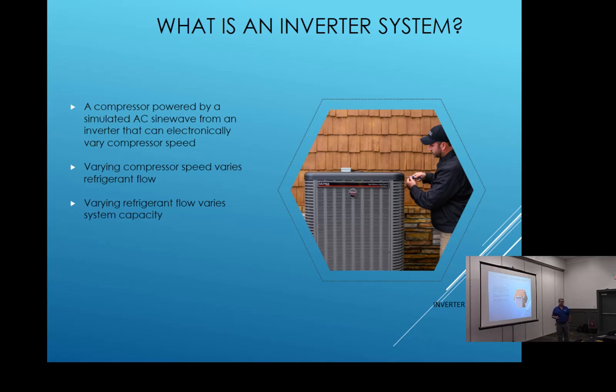Okay. Really, what we're doing is we're varying the hertz to that compressor. Just like a VFD drive, 60 hertz on the VFD drive is 100%, right? And if we go and turn the hertz down on that VFD drive to 55%, that blower, we slow it down to 50, it goes slower. Same thing. It's just varying it the whole time, okay, is what that basically is, in plain language from a Louisiana boy for me to understand. You know what I'm saying?